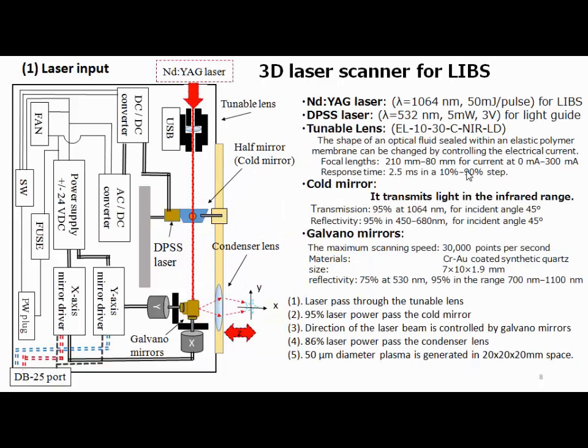This is the 3D laser scanning system and its specifications. When the laser enters from above, it passes through a tunable lens. The tunable lens is controlled by a PC via USB connection. The laser also passes through a half mirror, and then a galvanometer mirror is used for controlling the 2-dimensional position. The tunable lens and galvanometer mirror system enables 3-dimensional adjustment of the laser focal point.